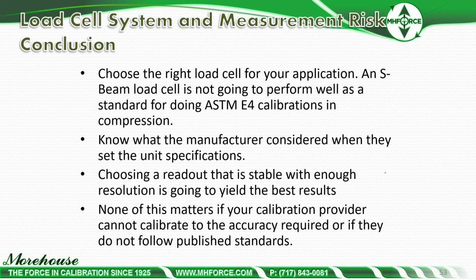I've heard of truck scales where they show the average. They have a truck drive by 3 times, they do 3 measurements, and then they report the average. Now in practice, you're not going to have a truck go circle around. You're not going to take the standard deviation of 3 measurements when you're measuring a truck to see if the weight is safe for the roads. It's just not going to be done. So you have to really dig into what the manufacturers are doing. Are they applying good metrology principles? Several are not. So it's a buyer beware scenario.